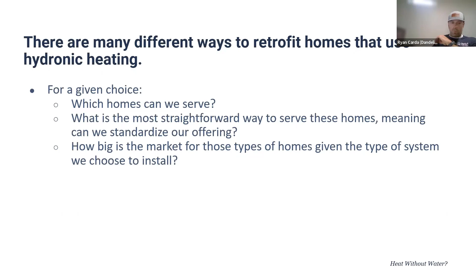When you're dealing with hydronics versus forced air, you try to balance what delivery temperatures you can effectively deliver to the home's heating distribution system. Hydronic baseboard and steam systems often require hotter temperatures than you can typically provide with a standard water-to-water unit.